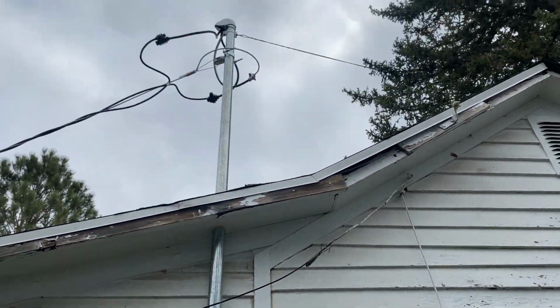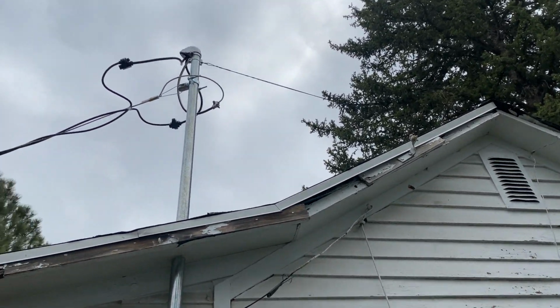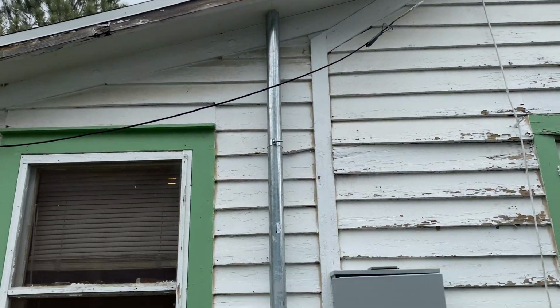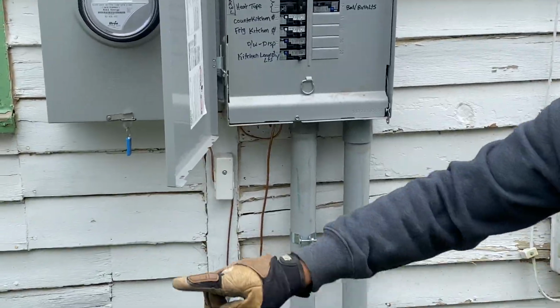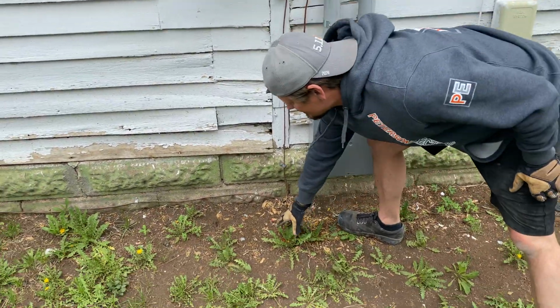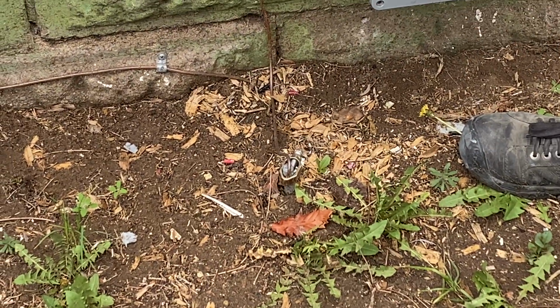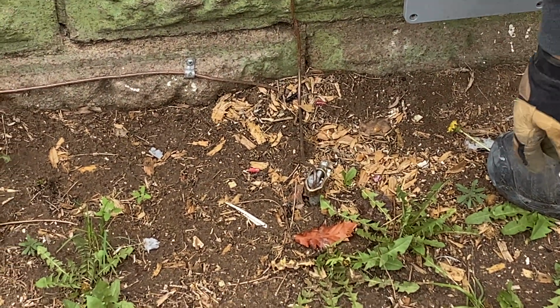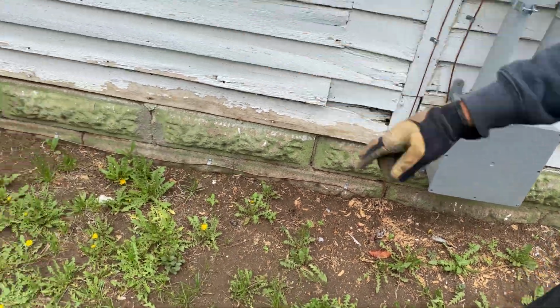Anyways, we put in a 2-inch overhead service mast, put a guy wire to protect it, to hold it, coming down to a bypass lever meter, intersystem bonding bridge bar, 2 8-foot ground rods. You have to see the acorn. The acorn, sorry guys, trash trucks always follow me. If the acorn is not present, it doesn't count. And there's 2 of them, one over there too.